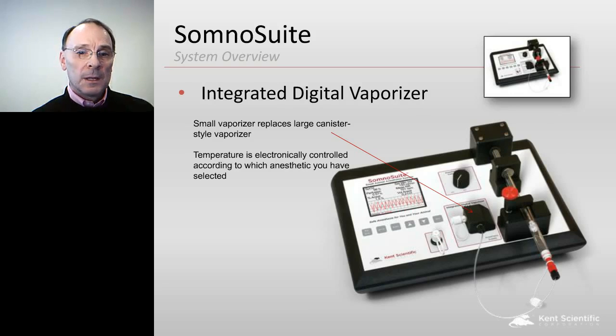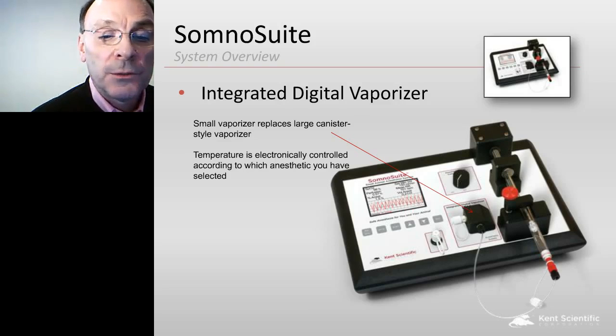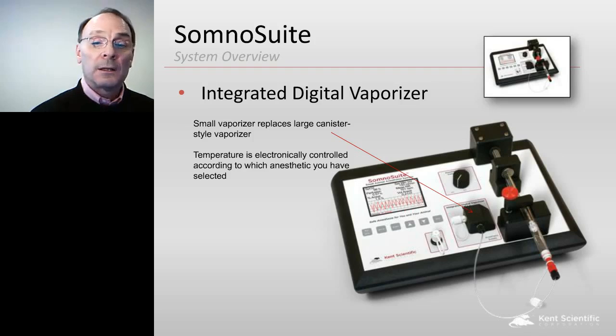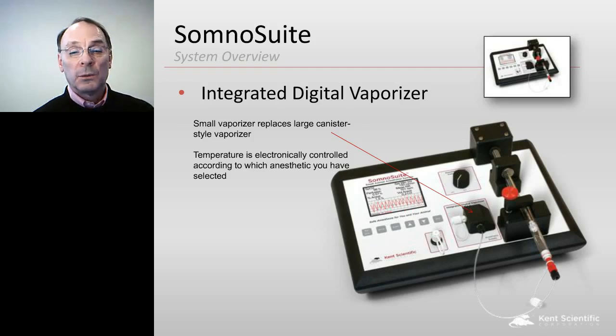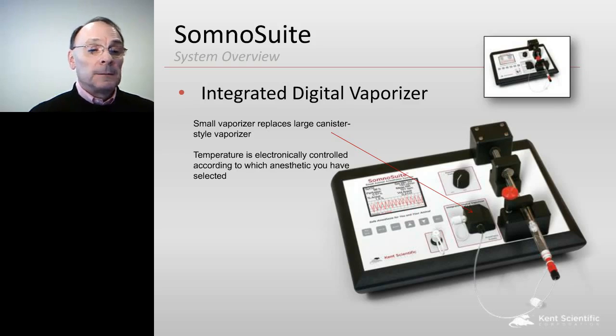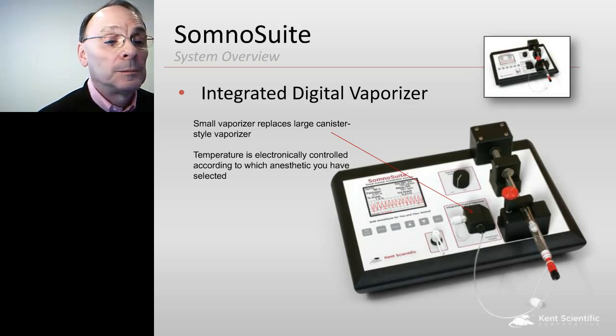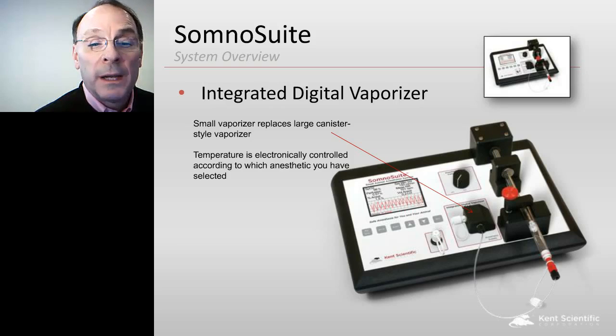And the annual maintenance requires that you replace the vaporization frit, which is just on the inside of the block, and which is a filter that we supply, but it's a sintered disc. This is from Russell Higbee from Sanofi again. Is it programmable by the end user?